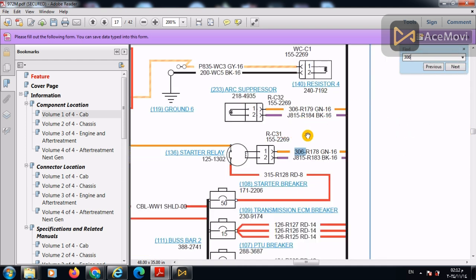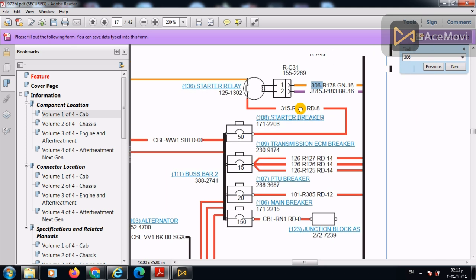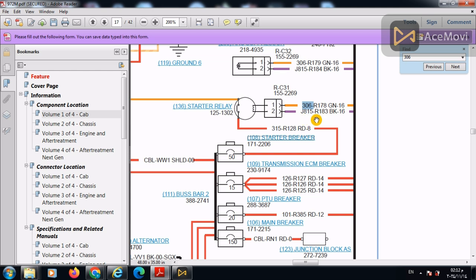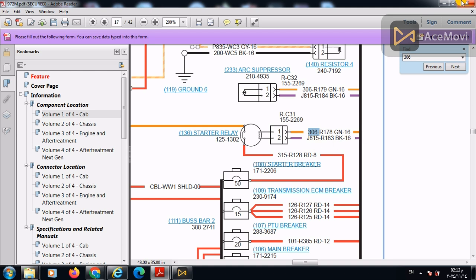So, here, as we have expected, this 306 is going to energize the start relay and eventually, we can predict or we can know that the other signal here or the other wire here is a negative ground. As also, you can see it in the upper arc suppressor that J815 is also common between the suppressor and the relay. So, we can predict that this is the negative ground.